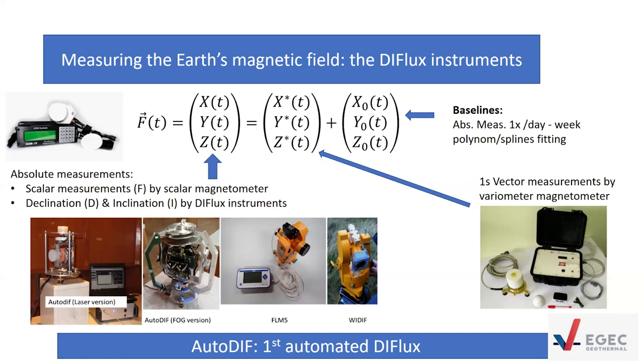But those instruments need some calibration, and this calibration is performed by absolute measurements. Those absolute measurements are made by a scalar magnetometer to measure the intensity of the vector, and by DI flux, which are measuring the declination and inclination of the Earth's magnetic field. So you see, to fully and accurately characterize the Earth's magnetic field, you need those 3 kinds of instruments. Variometer and scalar magnetometer have been automated instruments for a long time, but DI flux instruments have only recently been automated by our team here in the center.